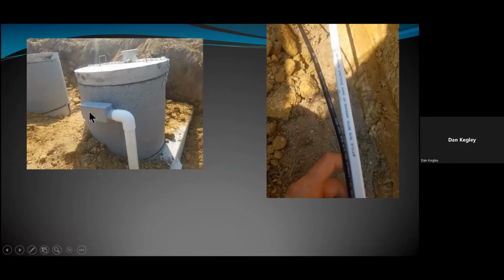So there's a lot of things going against this type of LL or LR box being used in this kind of scenario. And then you see the white plumbing pipe coming out, which is not rated for any kind of wiring at all. They do have short elbows for PVC conduit. Rather than long sweep elbows, they do make some short elbows for PVC, even though it's kind of rare to find, but they are out there. So a big telltale there is the white PVC versus gray PVC. It's not the proper PVC installed there. And I'm guessing they probably don't have any kind of frost movement or earth movement protection there, and probably don't have any fitting at the bottom for protecting the wires at the connection down below.